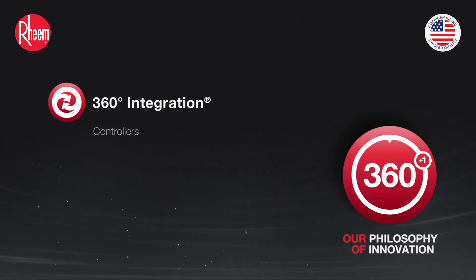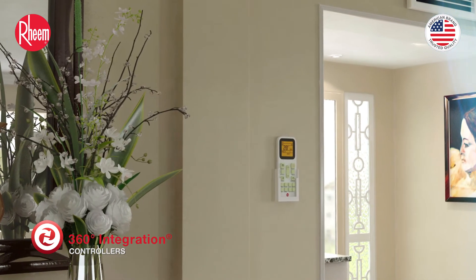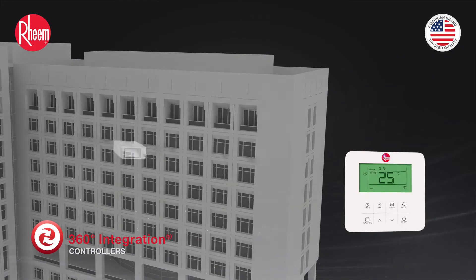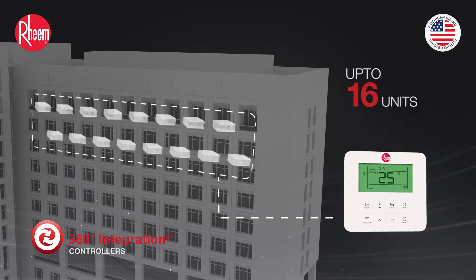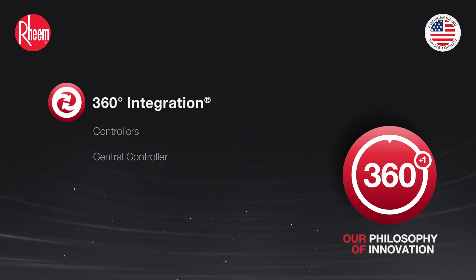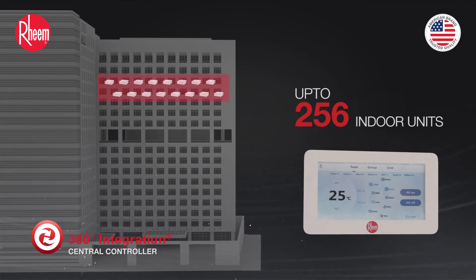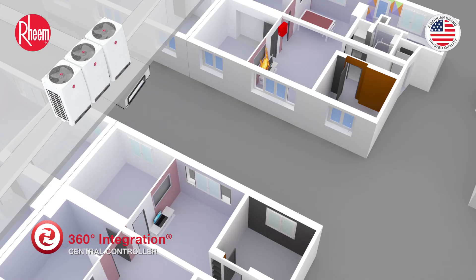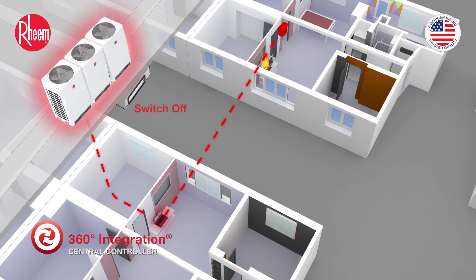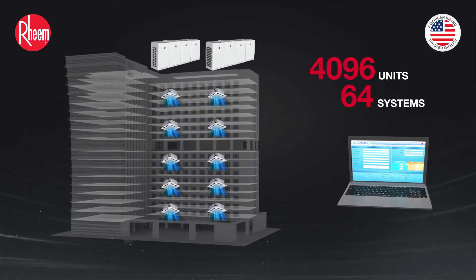360-degree integration. Rheem's modern VRF system provides various control options integrated at multiple levels. Touchscreen wired control for ducted indoor units can control units individually or up to a group of 16 units in the same system. An elegant-looking touchscreen central controller controls up to 256 indoor units from multiple systems. Controlling multiple units as a group or individually offers great flexibility in cooling large spaces. The central controller can take input from a fire panel to switch off the unit as required.